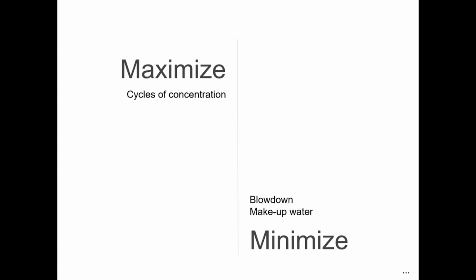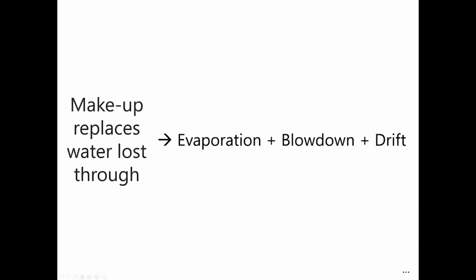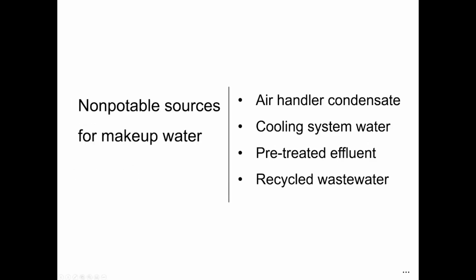So for cooling towers, we want to maximize those cycles of concentration and minimize our makeup water. Cooling towers are also a great way to use non-potable water that you're not using for irrigation. So if you're wondering, makeup, we saw that in the last slide. Makeup water replaces the water lost through evaporation just from the cooling tower running, blow down, and drift. And our non-potable sources for makeup water could be air handler condensate, cooling system water, pre-treated effluent, or recycled wastewater. So again, if you have recycled water that might not be potable, but you're looking to use it so it doesn't go to waste, cooling towers are another great option.